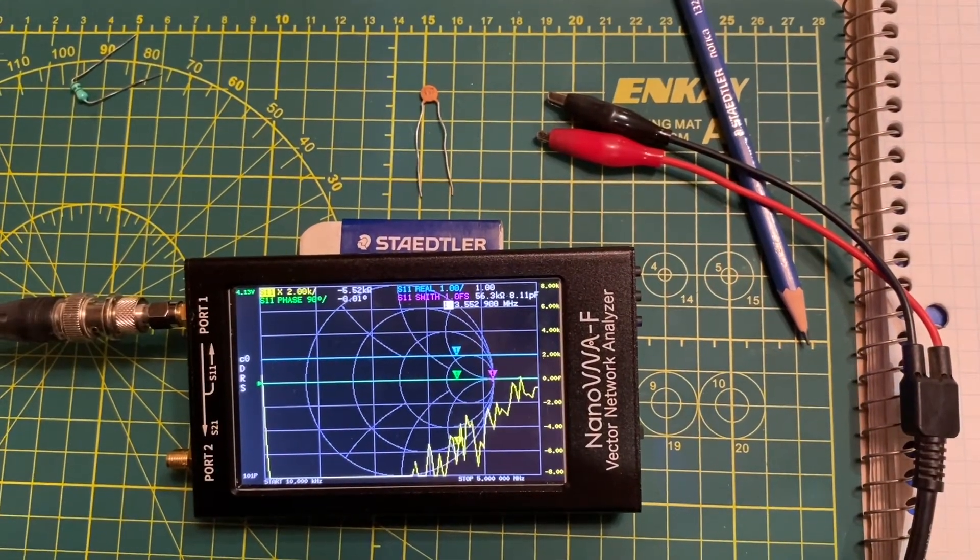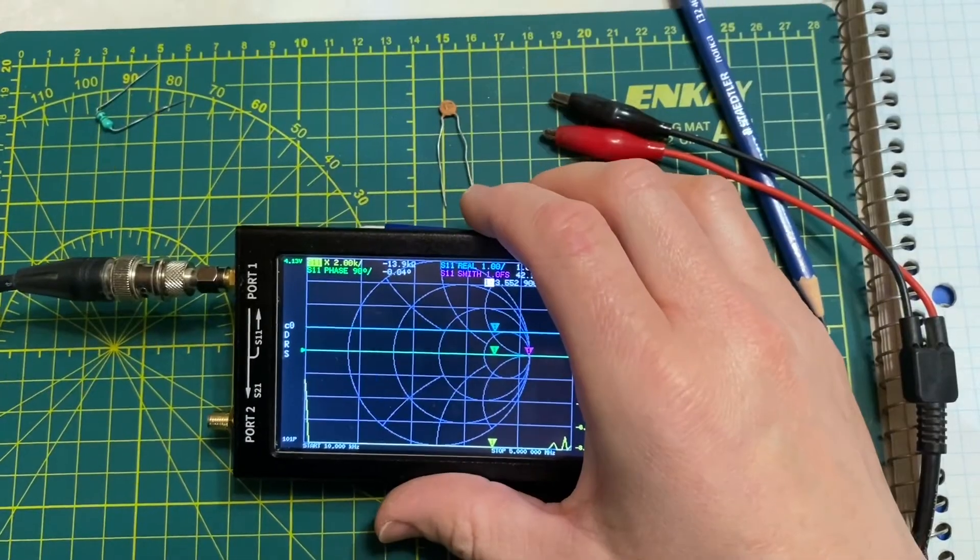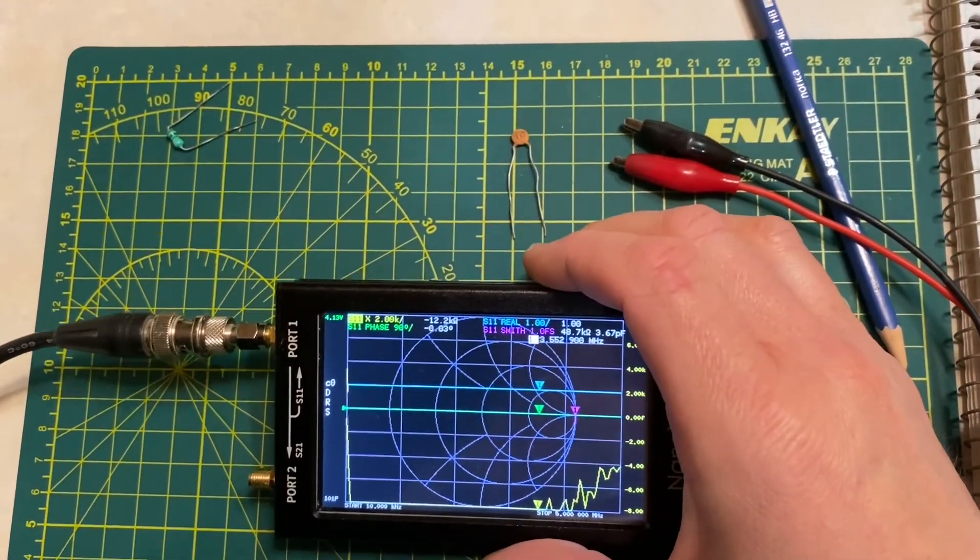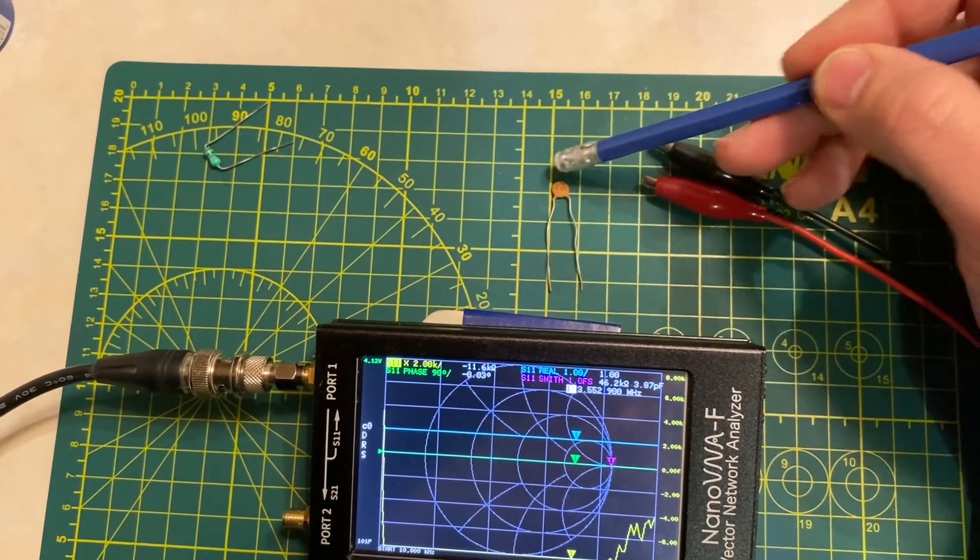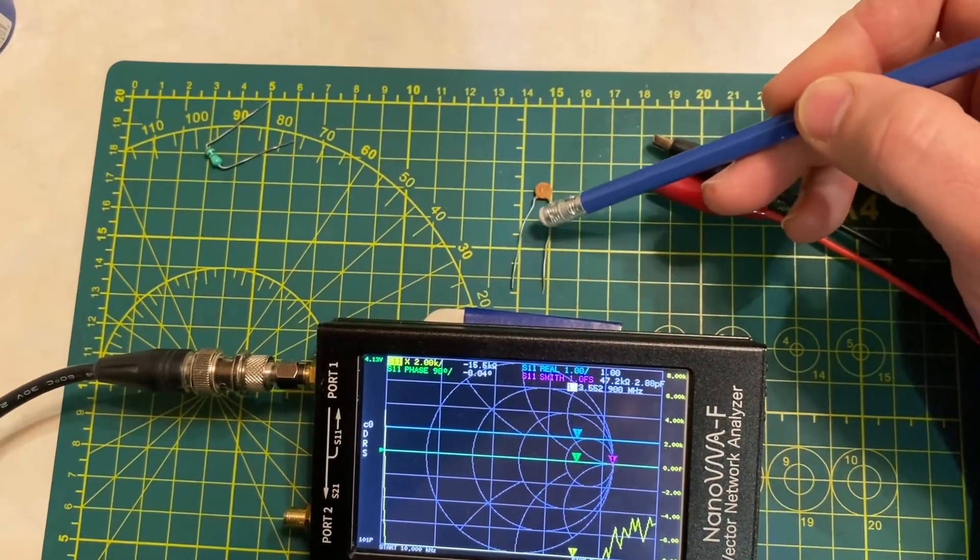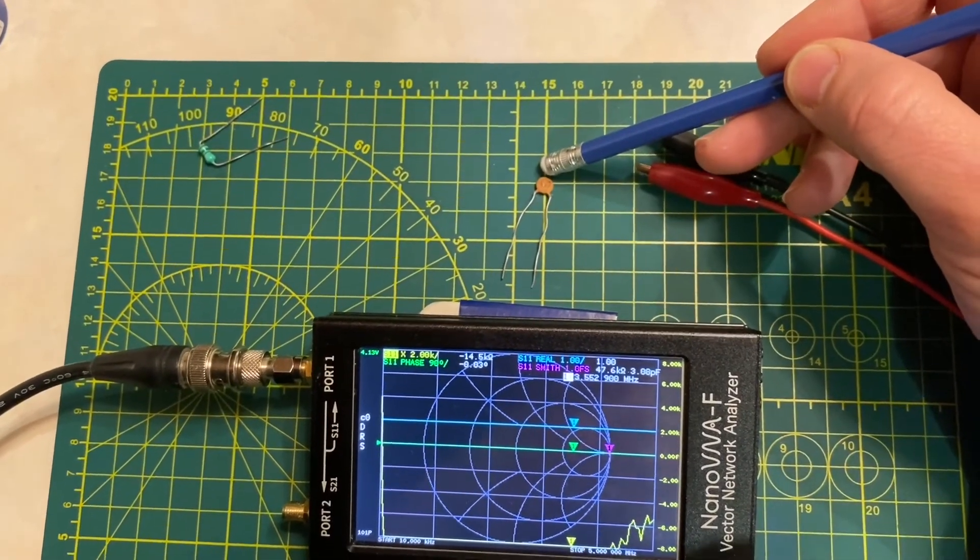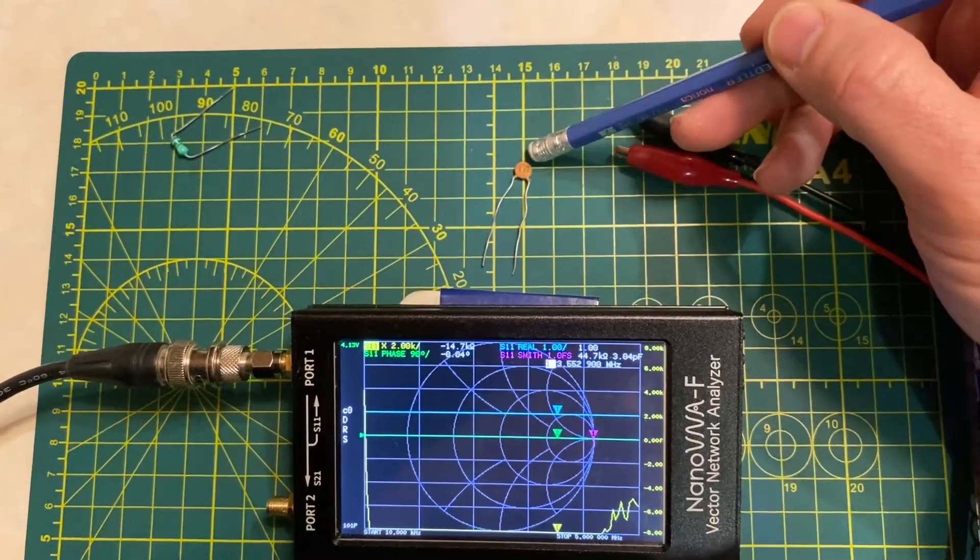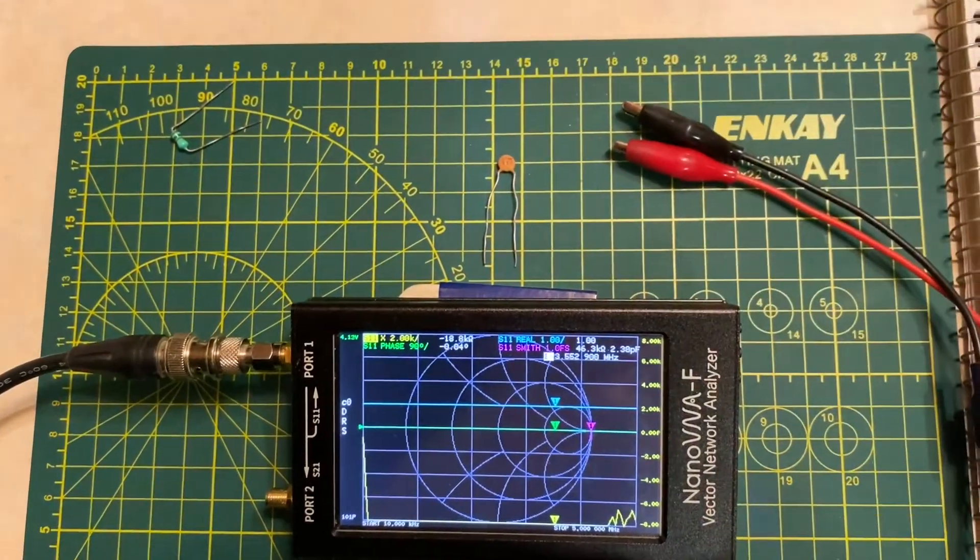Capacitors are well known to have a fairly broad tolerance range. If we take that value that we read off the capacitor, compare that to the value that's marked on it, and take into account that these things are good to plus or minus quite a range—I don't know exactly what this one is, maybe plus or minus 10%—I'm going to call that reading good.